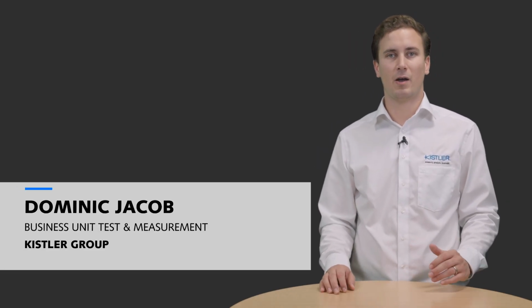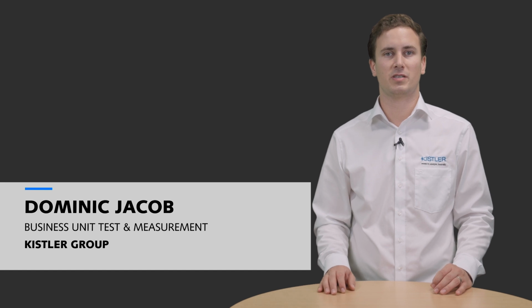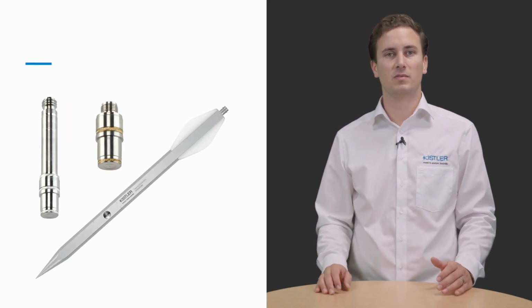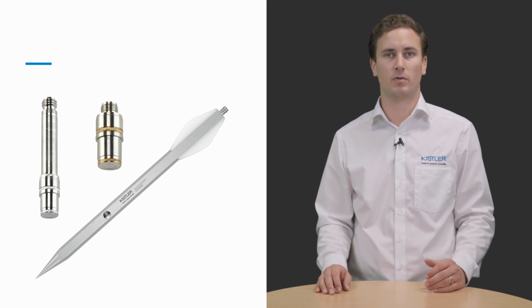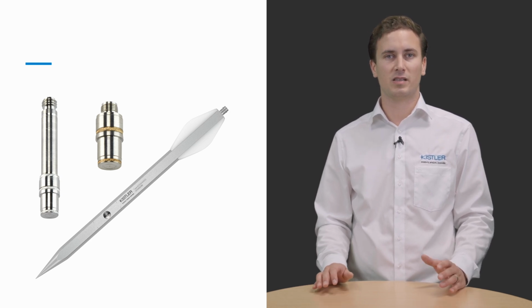Hello, in the next few minutes, I would like to show you how to best calibrate IEPE pressure sensors with short time constant, such as our 601C, 603C, and 6233B. These sensors are ideally suited for highly dynamic environments, thanks to their high-pass behavior, which will eliminate drift and DC offset while maintaining the dynamic components of the signal, such as pressure oscillations and shockwave fronts.